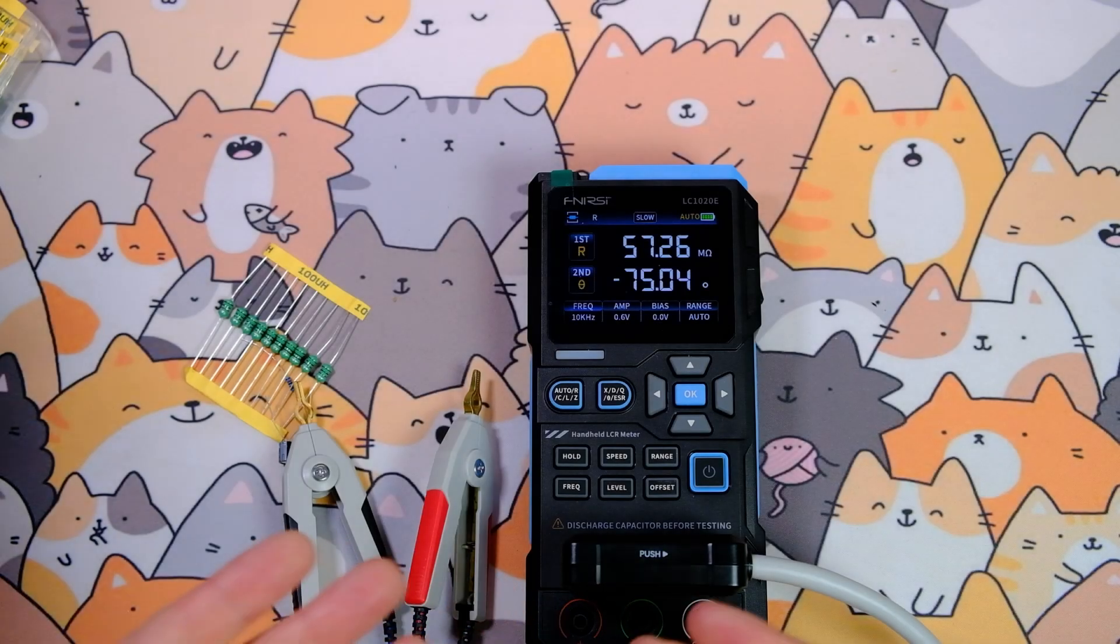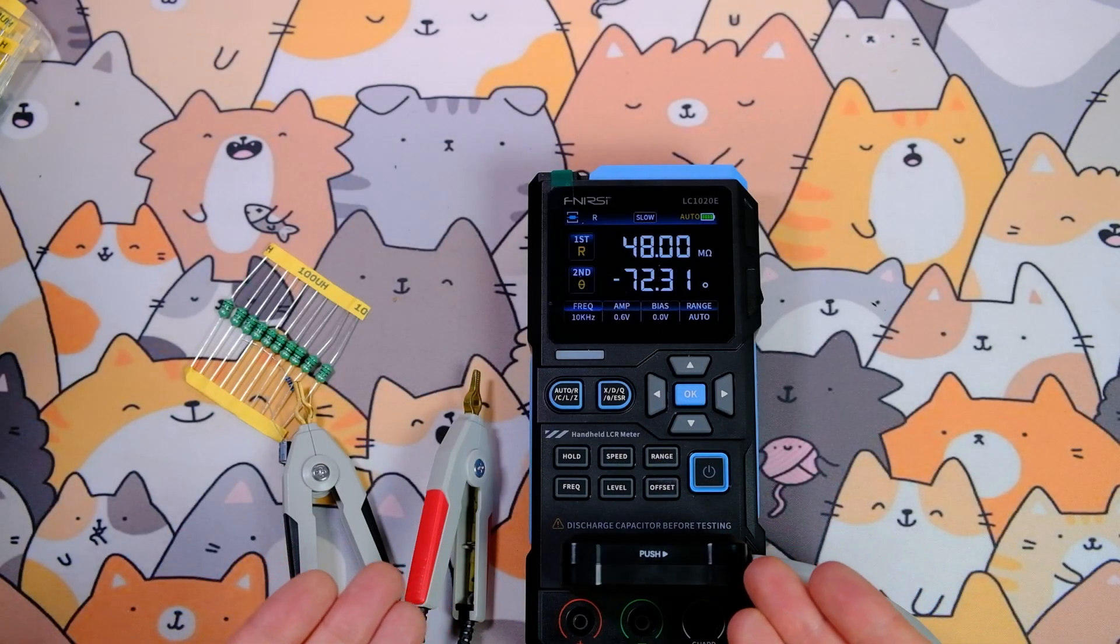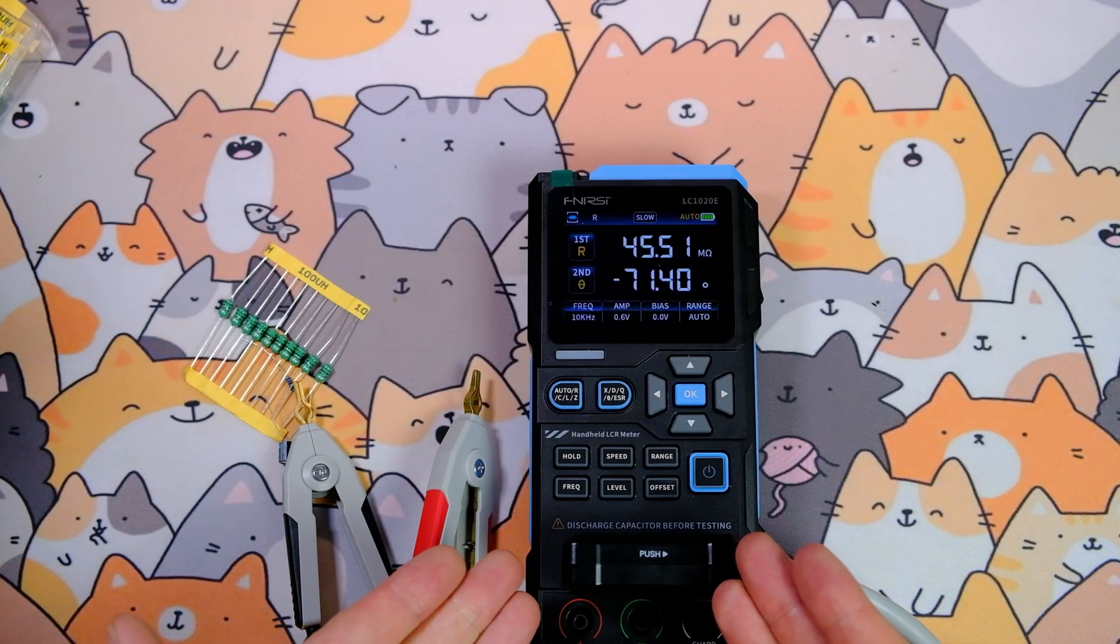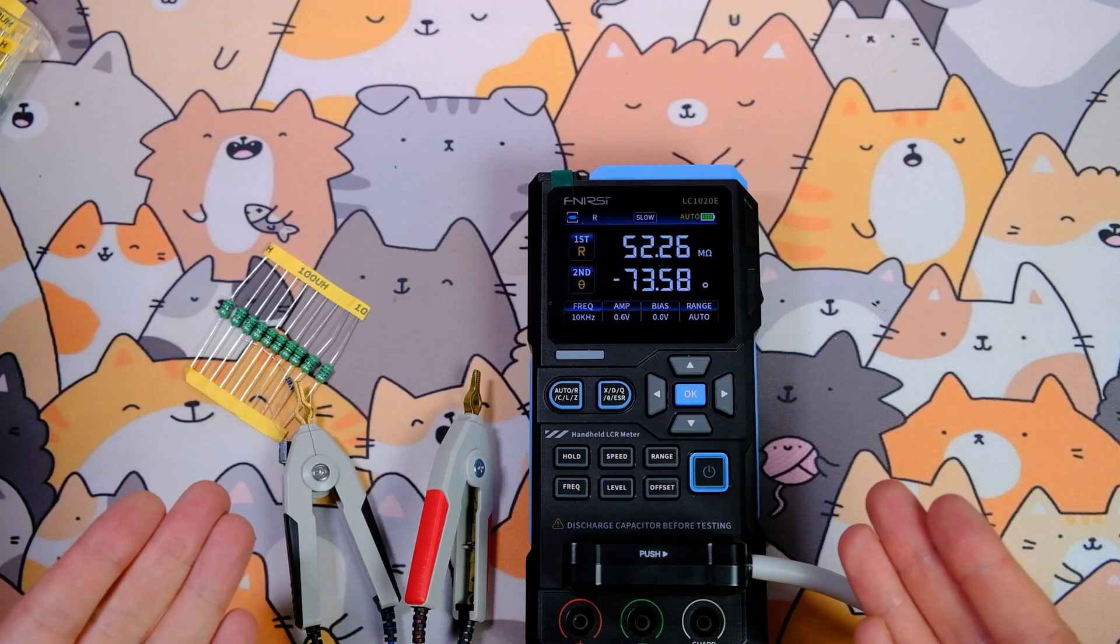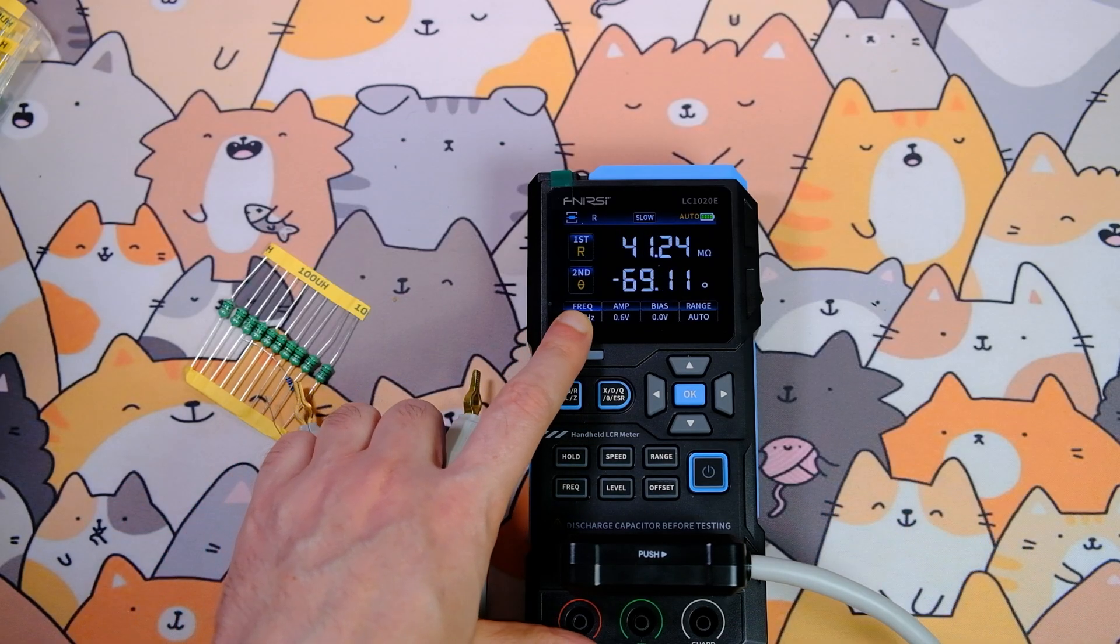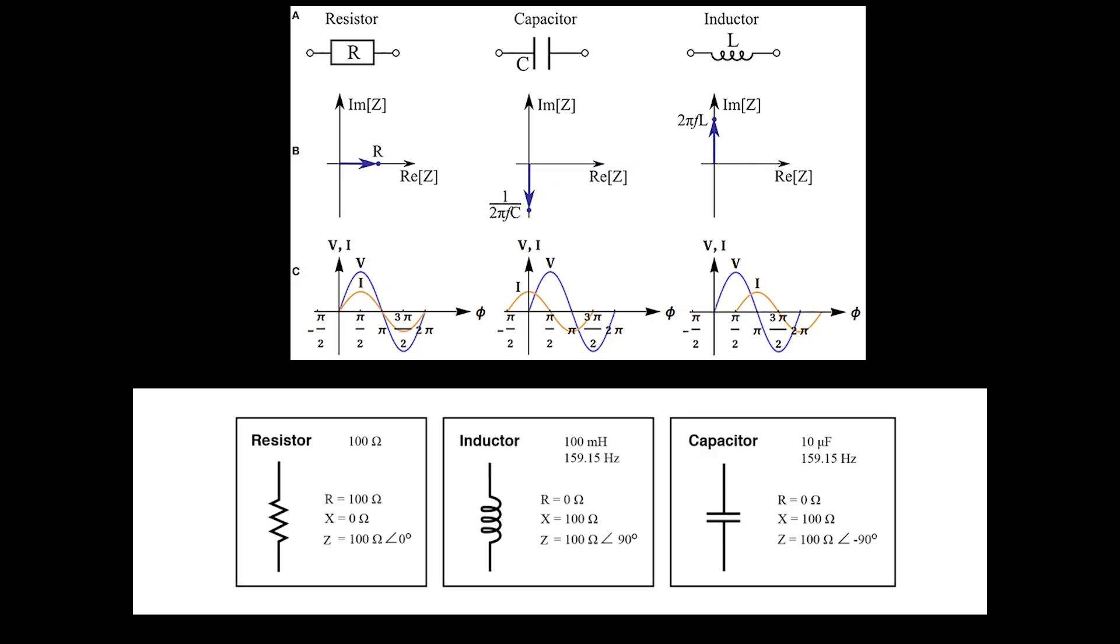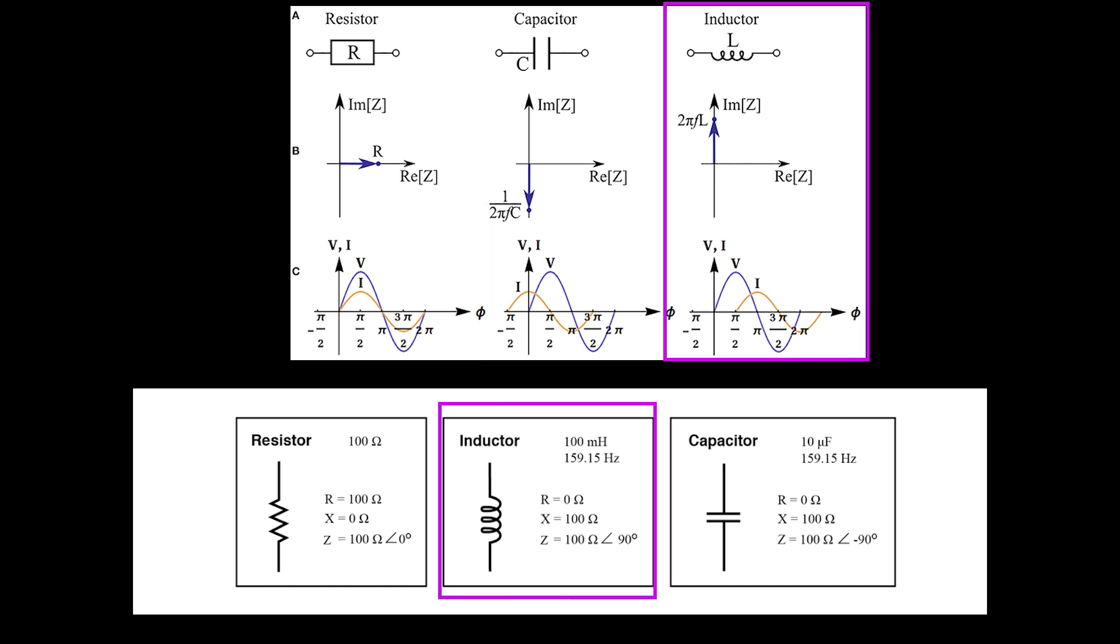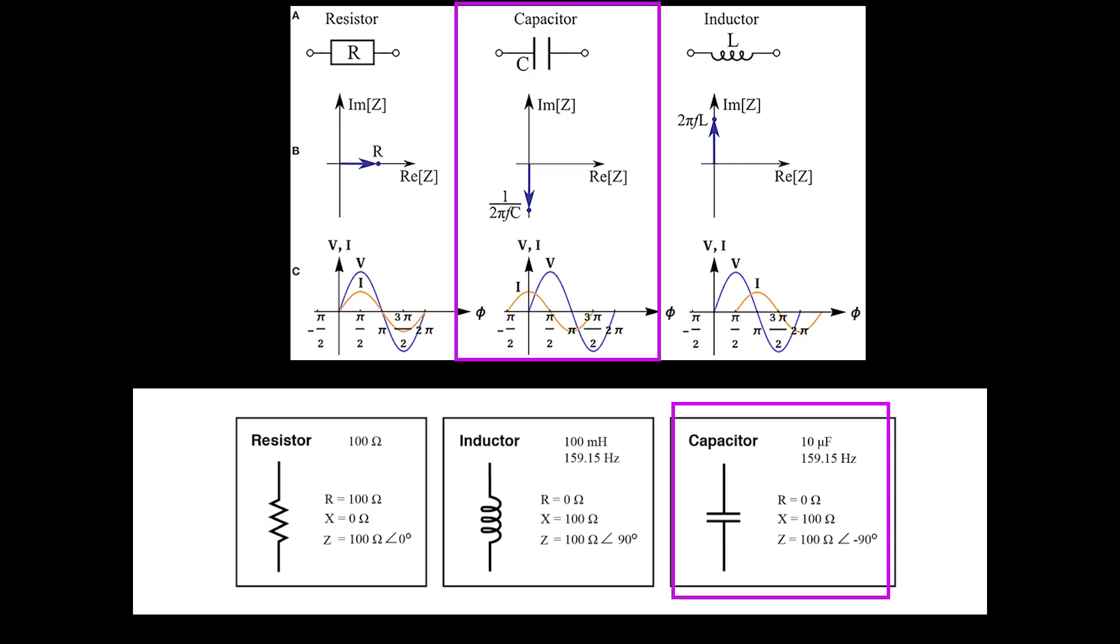LCR meters can not only measure inductance, resistance, and capacitance accurately, but they also measure additional parameters. For example, the phase angle, impedance angle. It's the phase difference between voltage across the component and the current through it. In an ideal resistor, voltage and current are always in phase, so the impedance angle is 0 degrees. In an ideal inductor, voltage leads current by 90 degrees, so the impedance angle is plus 90 degrees. In an ideal capacitor, voltage lags current by 90 degrees, so the impedance angle is minus 90 degrees.